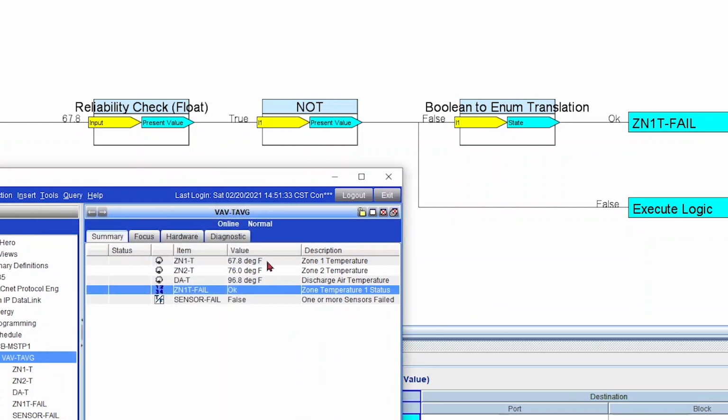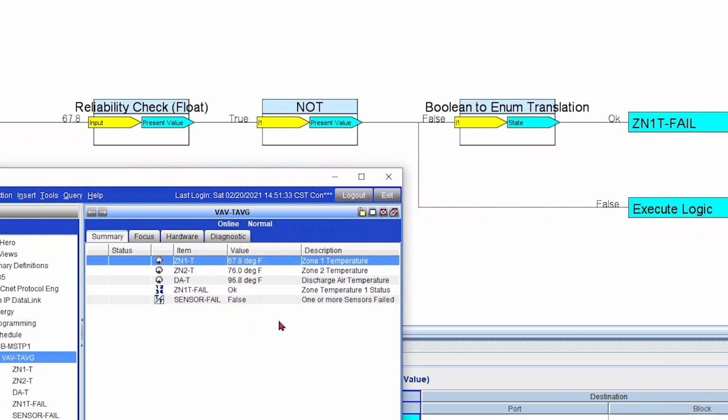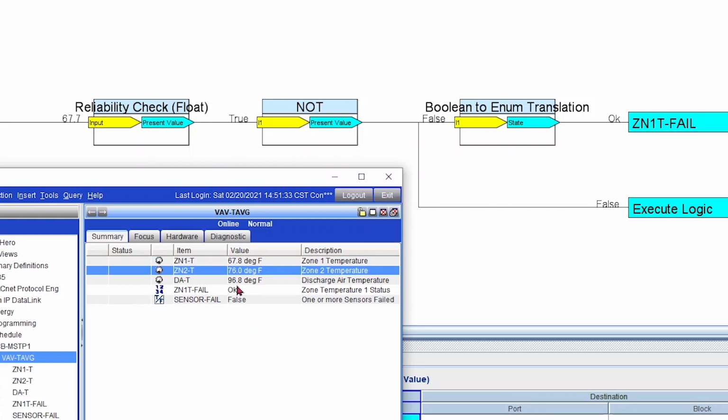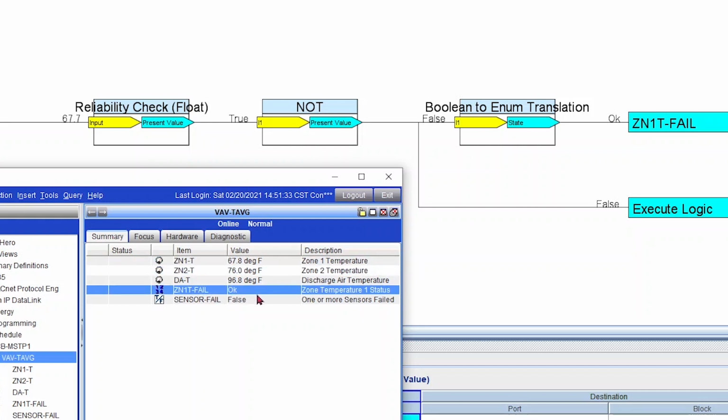And this sensor is sensor number 1, which is my thermostat. Now I'm gonna unplug my sensor, and notice that as soon as it goes unreliable, there's no way to tell in Metasys unless you have this additional point mapped. Alright, so my thermostat went offline, so I'm gonna acknowledge that. If this was not a thermostat, I wouldn't show offline if it was just a sensor on a regular input.